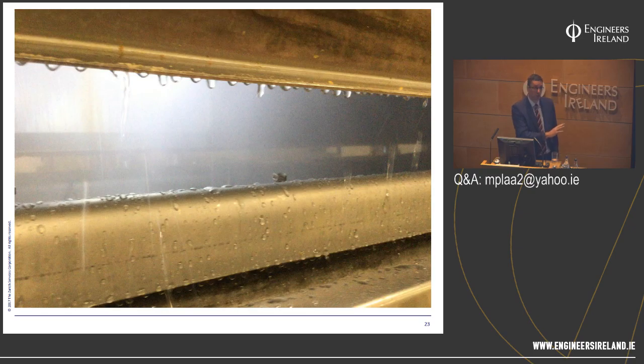So I'd really encourage you, if you come across water mist systems, if you can't be boots on the ground, get the client to video a test for you and demonstrate to you that that system will actually function when intended. I have done this on multiple occasions and have had nozzles with no water come out of them, and I've had pipework blow apart. I've had one industrial oil cooker project which took 4 attempts to get right. And we see lots of these in the field that have not been tested. The will it work bit is really, really important.